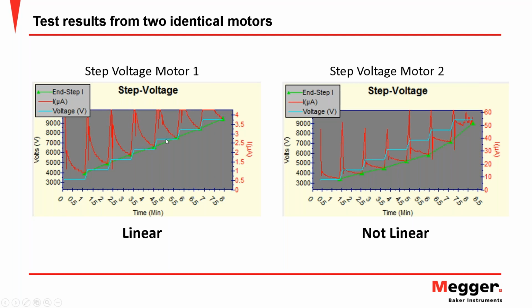These little spikes represent scale changes, nothing to be concerned about there. But we evaluate these final leakage current values in such a way that they basically line up in a linear way. And that green line that we can draw between those triangles represents the resistance of that circuit. And if the resistance is constant from the lower voltage testing here around 3,200 up to 9,200, this line will be straight. And if, as we see in this other curve on the right, it starts out linear and then begins to depart from that, that means that the resistance is starting to go down and that the insulation resistance is approaching its breakdown voltage.